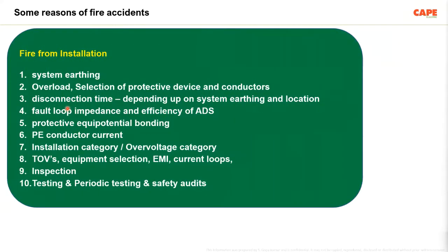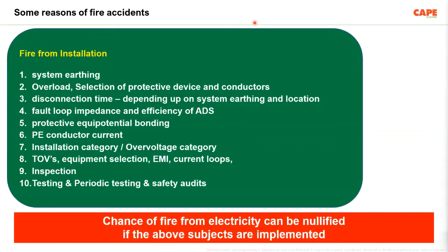So the 10 points which I wanted to stress, the important points which need to be implemented in an electrical installation, are: number 1, system earthing; number 2, overload protection and selection of protective conductors and devices; number 3, disconnection time. Depending upon the system, you should implement the disconnection time; fault loop impedance and efficiency of automatic disconnection; protective equipotential bonding; PE conductor current; installation category or overvoltage category; temporary overvoltages and the EMI current loops; inspection and testing. These are the 10 important points which I felt, if we do them properly, can actually reduce the number of electrical accidents very much in an electrical installation.